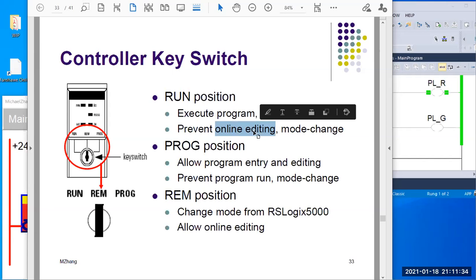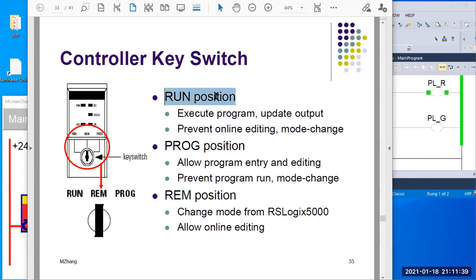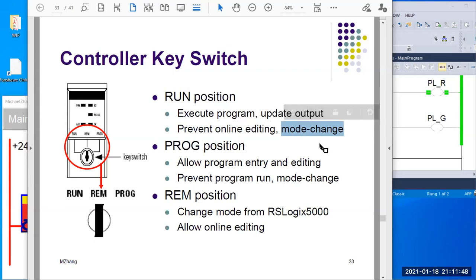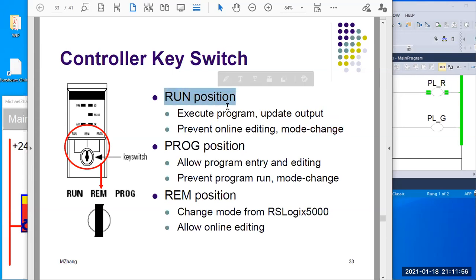We will have another video to talk about online editing. But if you have the key switch in the run position, you cannot do that — you cannot even change the mode. So basically in the run position, nothing will change on the current status of the PLC controller. You just want to run the production. Like if you want your machine to start running production with no more changes, you can put the key switch into run position, then unplug the key, and then nobody can do anything on your PLC controller. That's basically a sort of safety protection.